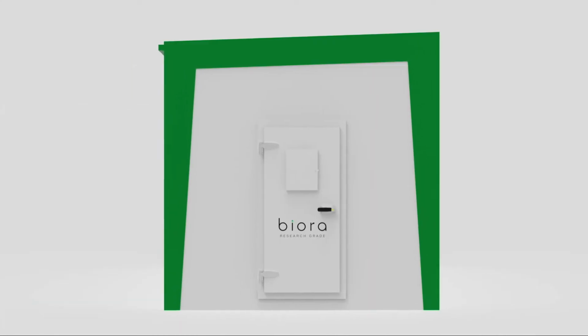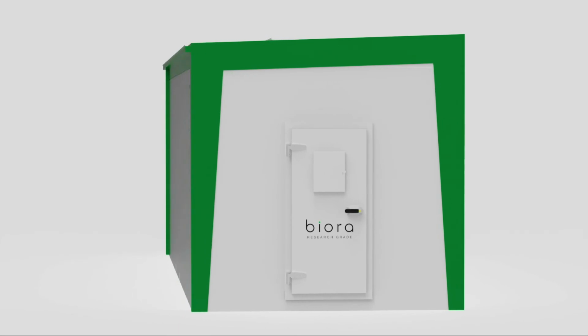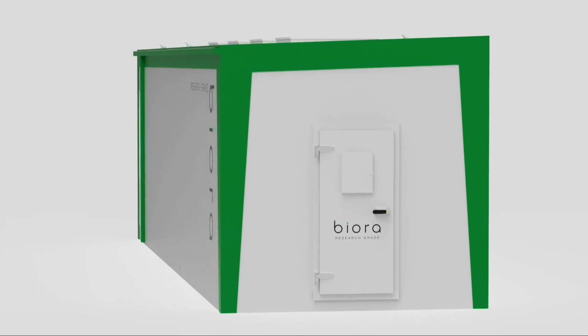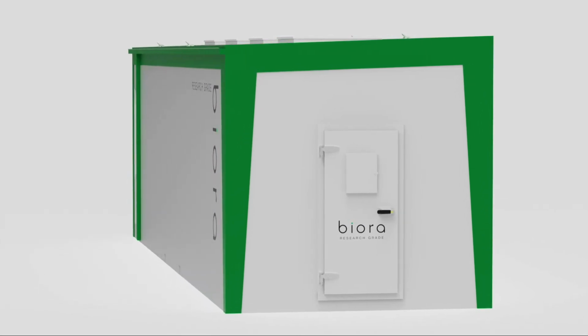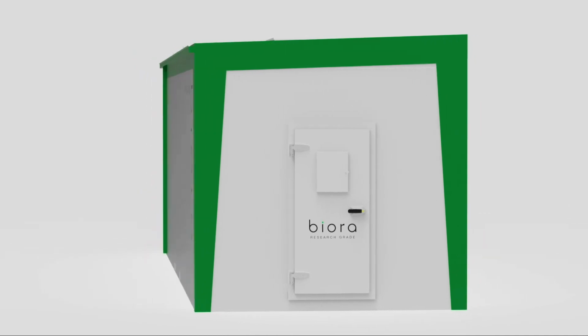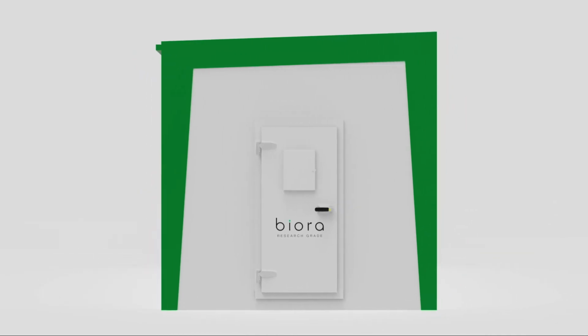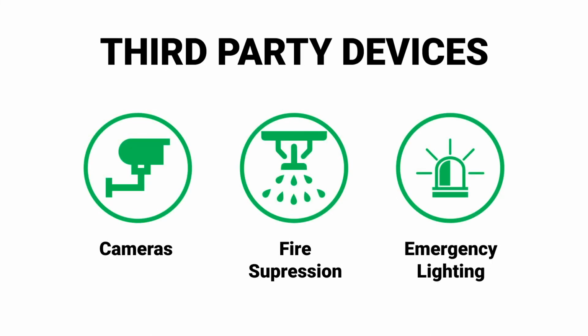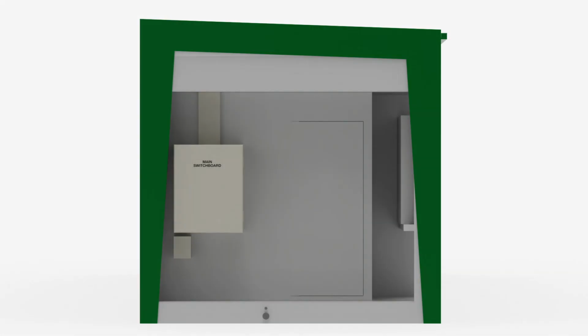The design allows a sloped roof with guttering and downpipe that can be fixed to a stormwater connection or soak well. All doors are lockable, with access controlled via an RFID access. The chamber can be fitted with third-party devices such as cameras, fire suppression systems, and exit and emergency lights that are cabled back to the switchboard. In summary, here's another quick view of all sides of the Biora chamber.